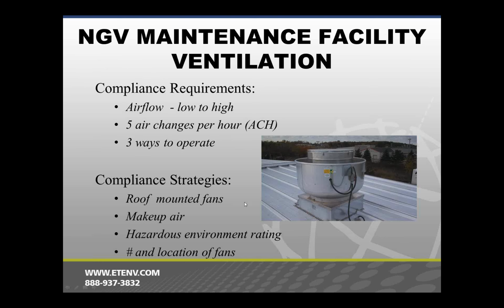The compliance strategies are usually roof-mounted fans like you see in this picture. One thing about the roof-mounted fans is we know that they're going to be turning on and exhausting air after a detection, for example. And for that reason, we want to make sure that these fans are rated for that environment, meaning they have non-sparking fans and their motors are electrically safe, or at least not in the airstream of that hazardous air that may be exhausted.